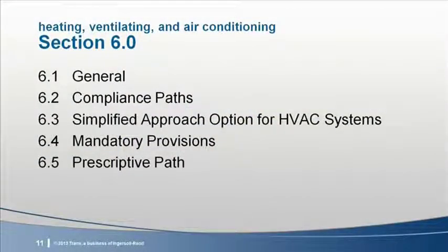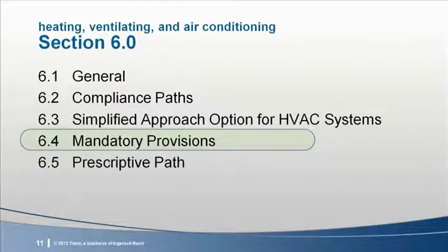Before we look at the actual wording of the 90.1 standard, I think it's important to point out that the requirements for SingleZone VAV control are included in the mandatory provisions of Section 6.4. This means that you must comply with these requirements, whether you choose to follow the prescriptive path in Section 6.5 or the energy cost budget in Section 11. In addition, if the project qualifies to use the simplified approach described in Section 6.3, the same requirement for SingleZone VAV control applies. Now, let's look at the requirement from Standard 90.1.